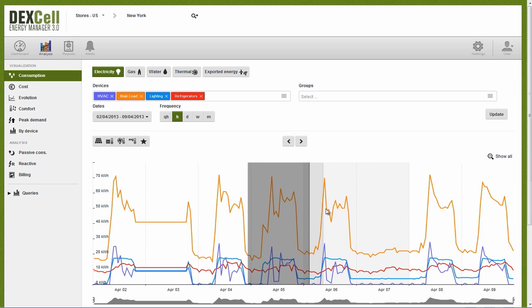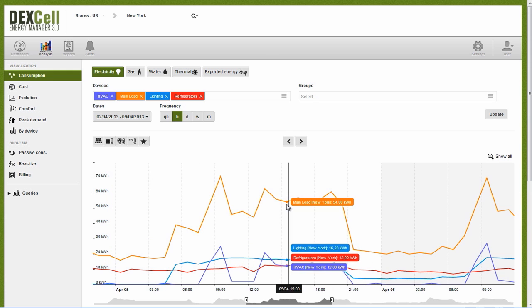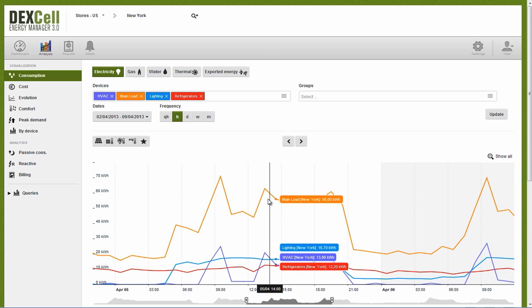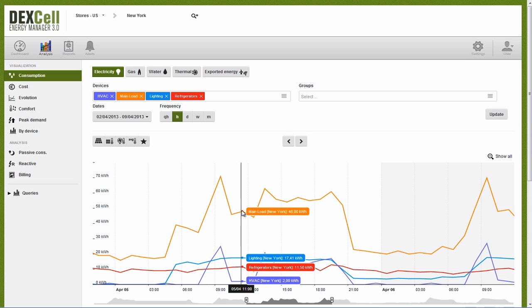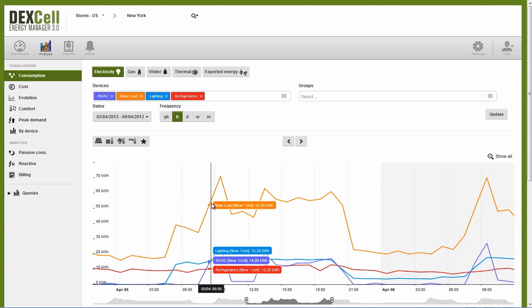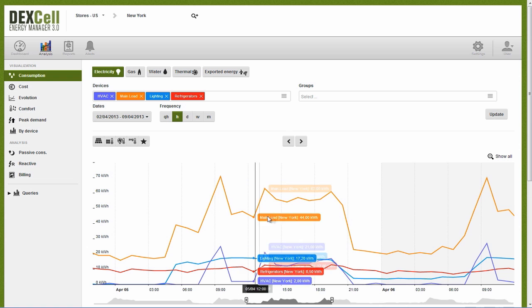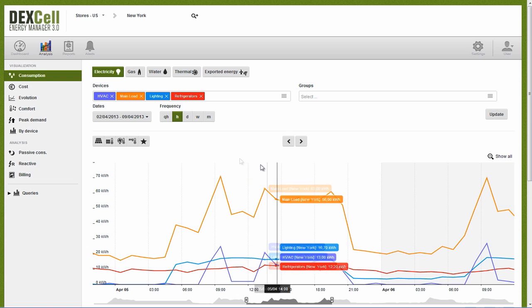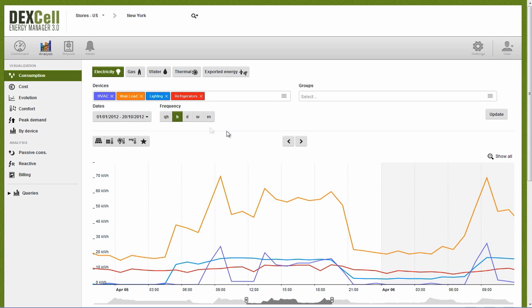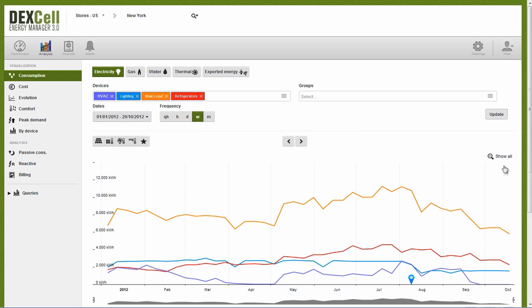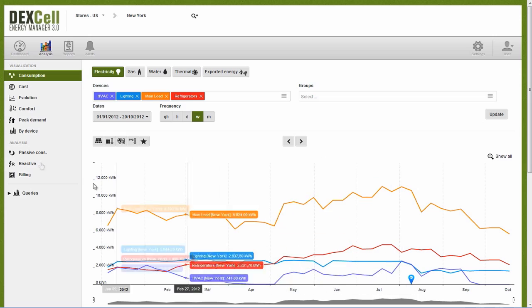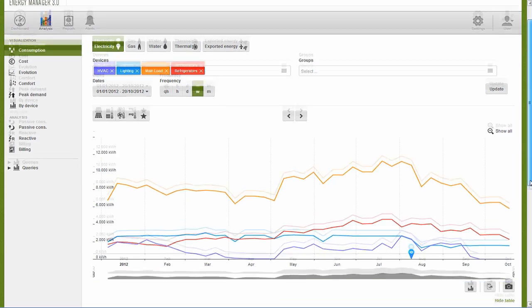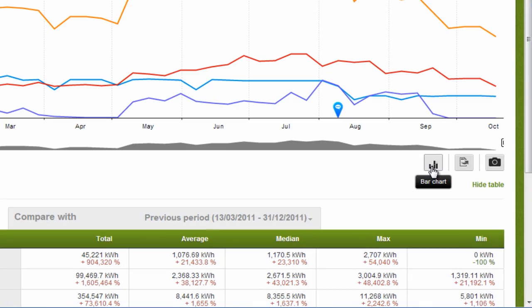We can see here that refrigeration levels are constant, but they should be changing according to outside temperature. We can also view the evolution of energy consumption for each individual meter from week to week. If we select a date range and choose to view weekly consumption, DEXCell Energy Manager displays an overview of the consumption trends of facilities so we can identify patterns. All data and graphics can be exported to Excel for future reference or graphical reports.